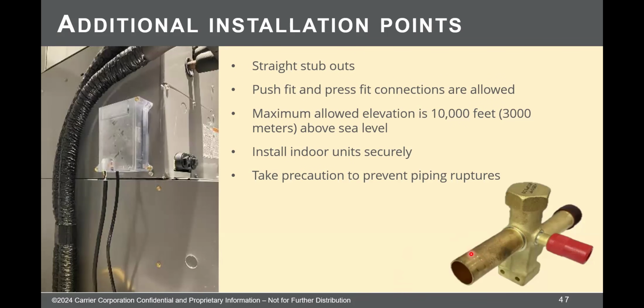The reason that they're straight instead of swedged is that they are now designed to be used with press fittings. You are still allowed to braze. This question's come up a lot. I've had several guys in class tell me that our stores have said, no, you can't braze anymore. You gotta do the tool thing. You don't have to do that. You can braze. Brazing is allowed.